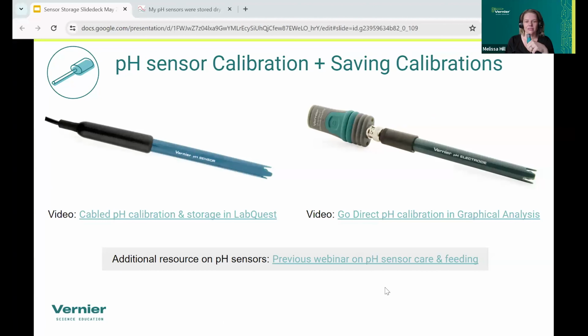and watching that. Oh, one other thing I do want to mention: when you go to calibrate, if you bring them out in the fall or next month for your summer research project, you can store calibrations to the sensor. With the Go Direct, they store automatically. With the cabled sensors, you have to do another step in software, but all of that is shown in those videos. So don't think you have to calibrate them every time you use them. You can store that calibration. And storing a calibration should last quite a while, especially if it's a well-maintained pH probe. But once you start to see data that doesn't look good, or again, if that pH storage solution is outside the 3 to 5 range, you need to recalibrate and give it another go.